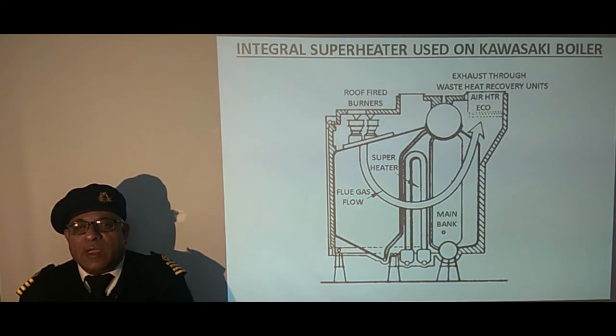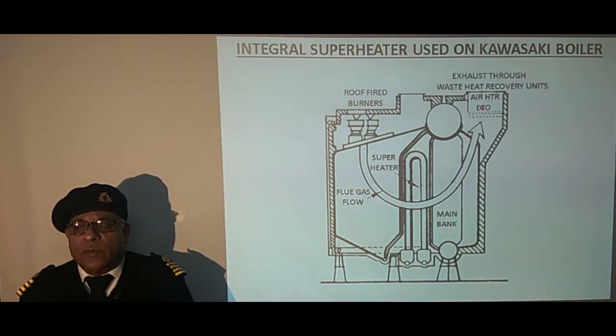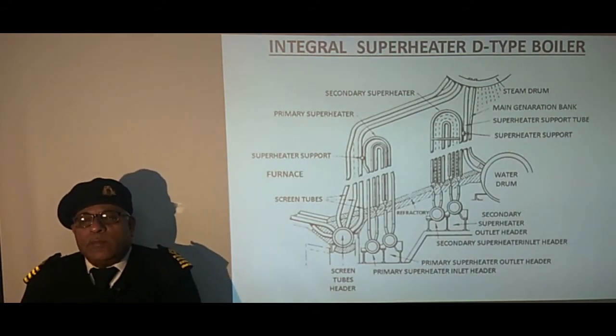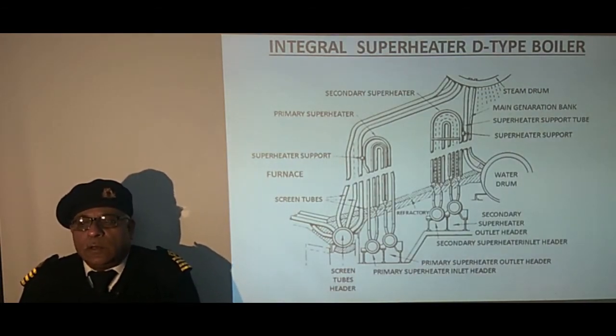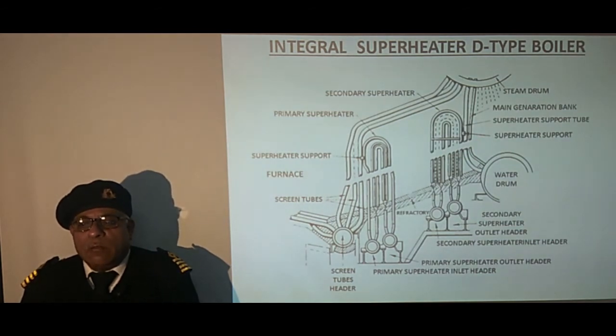This is the main generating bank. Before leaving, the gas passes over the economizer where feed water is heated, then goes to the air heater where combustion air is heated, and leaves the boiler uptake. The D type boiler is equipped with two superheaters, which is a common arrangement in most modern boilers for having better control over the degree of superheat by using an attemperator between them.